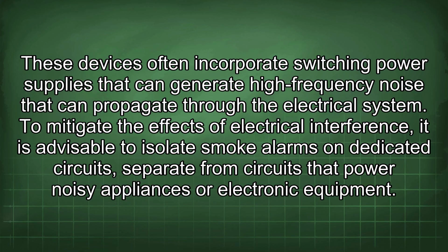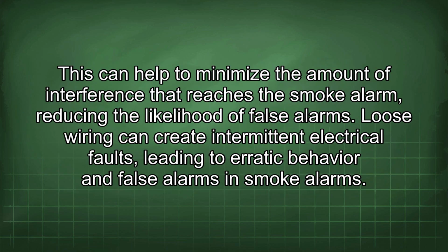To mitigate the effects of electrical interference, it is advisable to isolate smoke alarms on dedicated circuits, separate from circuits that power noisy appliances or electronic equipment. This can help to minimize the amount of interference that reaches the smoke alarm, reducing the likelihood of false alarms.